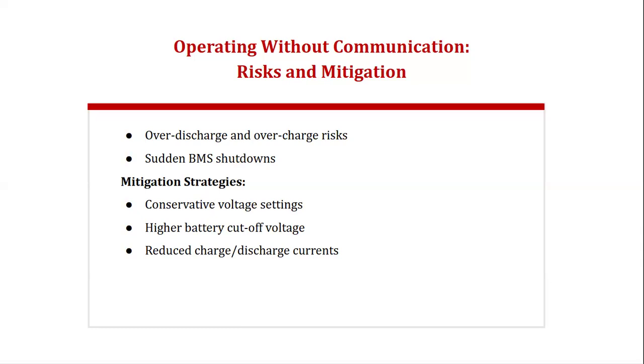Conservative voltage setting. You would have to set the voltage on the inverter: please, inverter, as you are draining the battery when my client is using it, when you get to a value that I'm going to set, please stop. Give an alarm at that point that the battery is low, then stop finally. That value will be the low battery cutoff point, but it's going to be a little bit higher. Generally, it's about 48 volts. If you don't do that, by the time the battery goes below that and goes down maybe to 42, because it's not communicating, it won't wake up. When you now have sources to charge the battery, it won't wake up. In fact, the battery will protect itself by disconnecting from the inverter. So the inverter will no longer recognize that there is a battery.